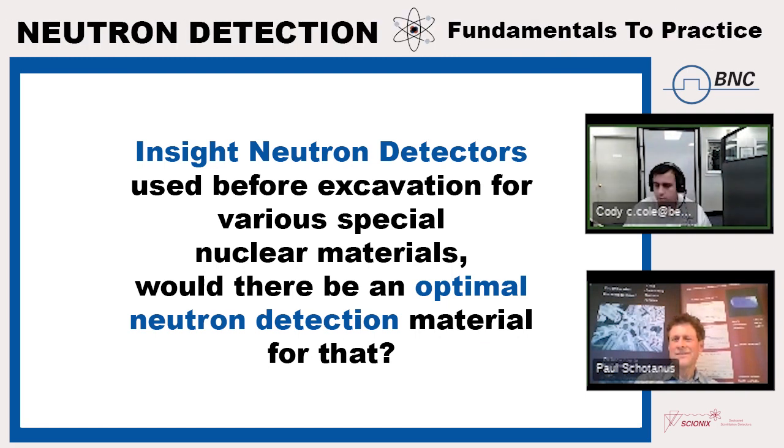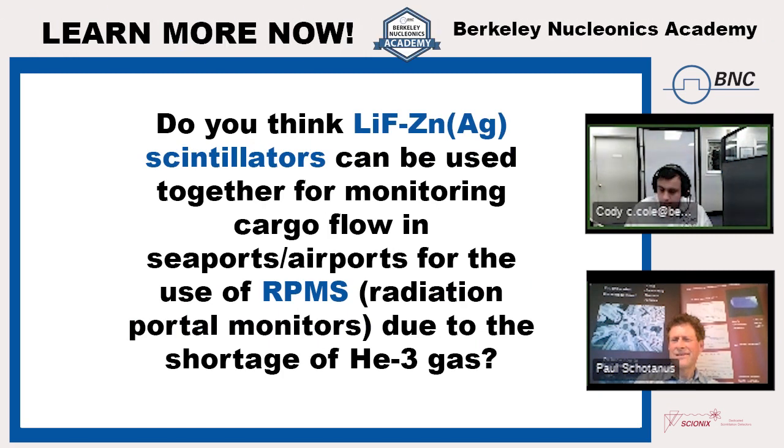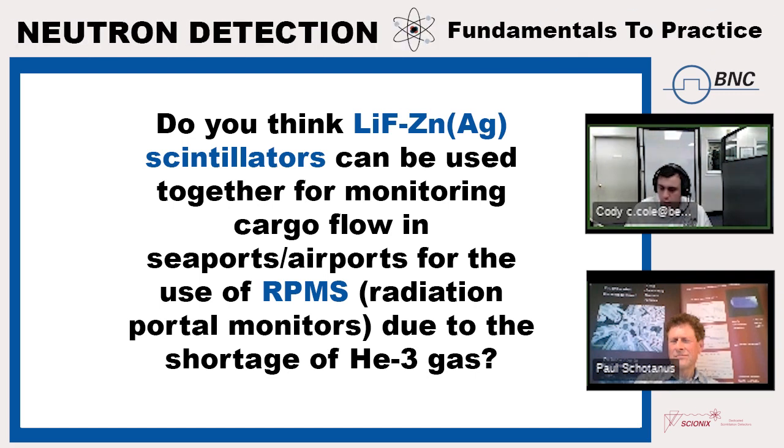All right, so from Haluk, he is wondering if you think, sorry, the question jumped. I have to scroll back up. Do you think that lithium fluoride-ZnS(Ag) scintillators can be used together for monitoring cargo flow in seaports and airports, as radiation portal monitors, due to the current shortage of helium-3? Yeah, definitely. Yes. Oh, awesome.